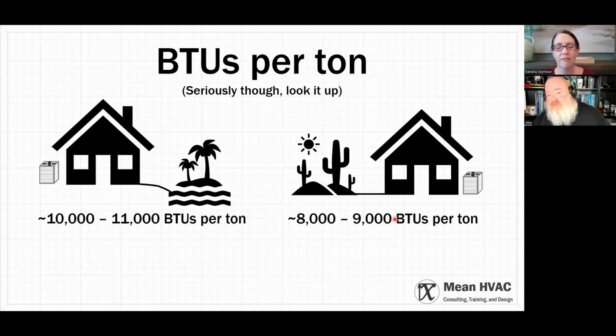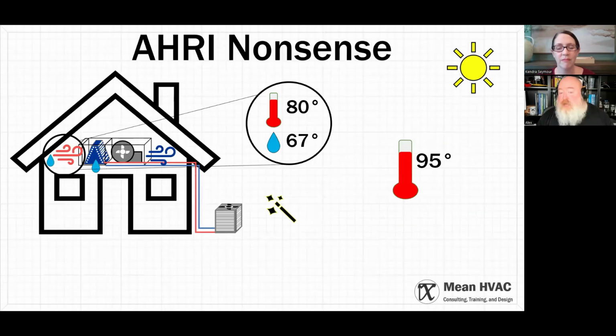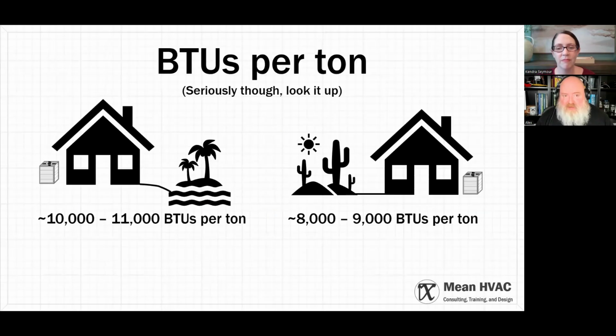There are so many contractors in the greater Phoenix area who do their first load calculation and go, no way, because they look at the BTUs and they look at AHRI, and there's no way that system would ever work in that house. They're right. It's because that system doesn't give them anywhere near that many BTUs. If they looked up the detailed data, they would see, oh, this thing sucks at doing air conditioning in a hot climate, I have to pick a bigger one. So they're right, they have to pick a bigger one, but it's not the load that's the problem, it's the performance of the system.